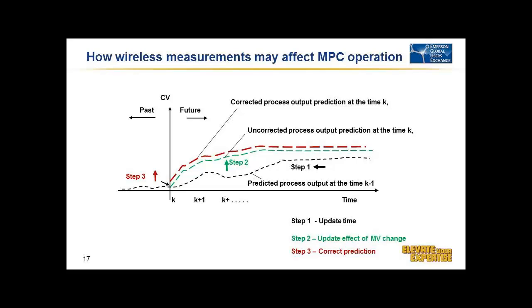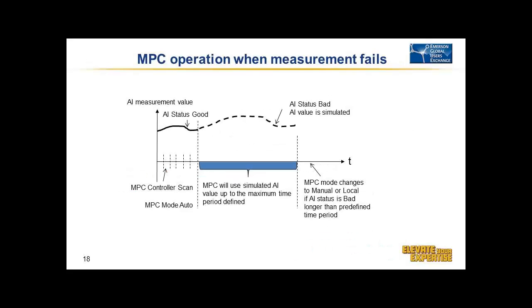Another feature we realized at that time, and definitely we knew of those features, is that essentially that principle is already applied in MPC. One of those features which we have in Predict Pro is that when a measurement fails, MPC can work for a certain period of time, and we pre-program that period of time based on the model.